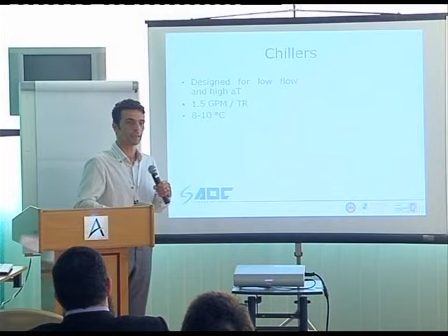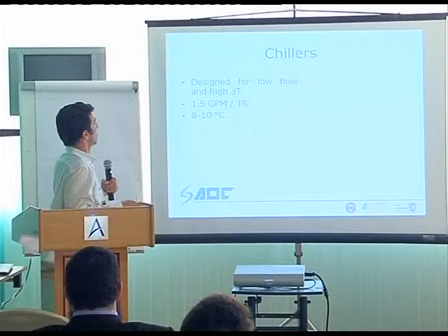So we make this mule we have, called 1 kilogram of water, carry more kilojoules for us than just one. If I circulate it on a delta T of 1, it means I can only carry 4.2 kilojoules in it. But if I make it carry 10 degrees Kelvin - it should be Kelvin, but for some reason these guys keep it in degrees C - you understand that too, yes? Okay, with 10 degrees Kelvin in it, I can carry almost 42 kilojoules of energy in 1 kilogram of water. That's a good amount, that's almost 42, that's 12 tons or something.